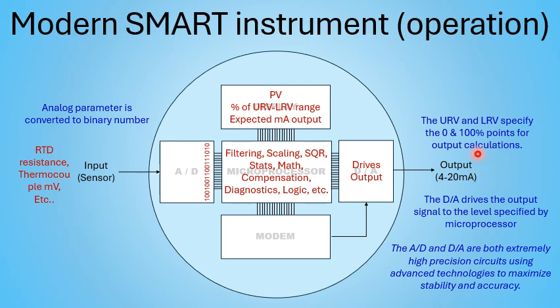And I have blogs talking about that. Everything from a little bit of water in a J box or in a conduit run, the typical PLC analog input cards actually drift. They drift faster than these instruments, ironically. No one seems to know that, but they do. You can look at the specs.